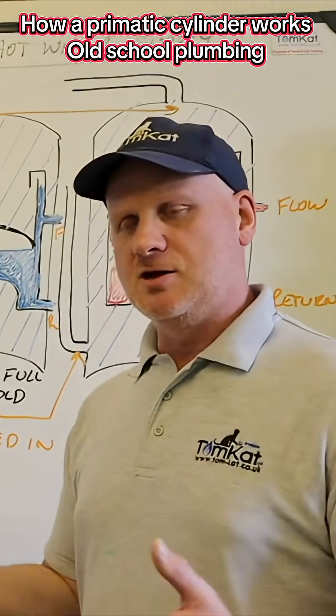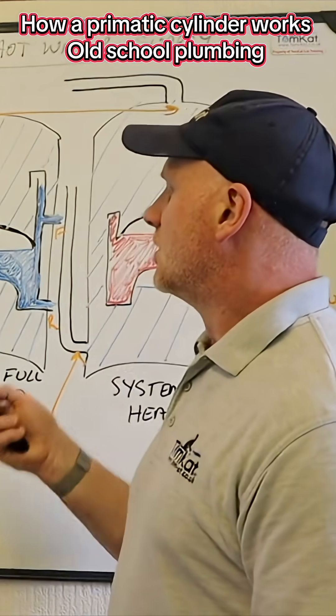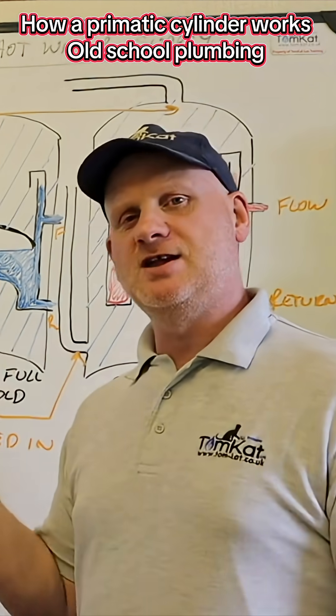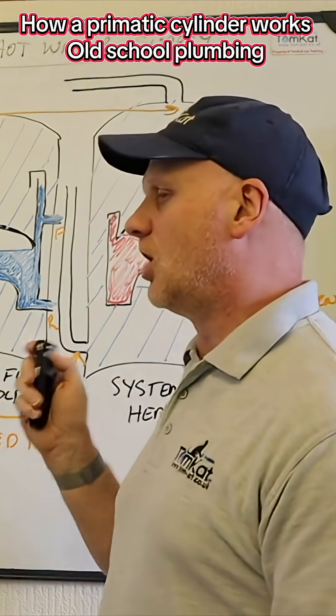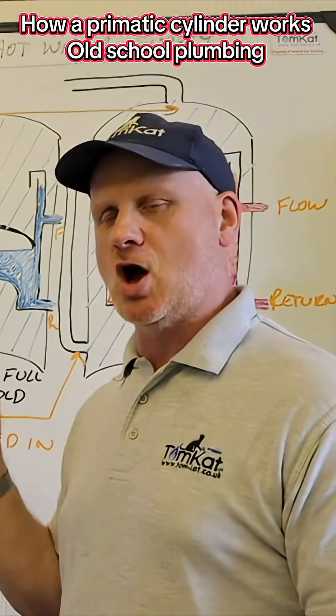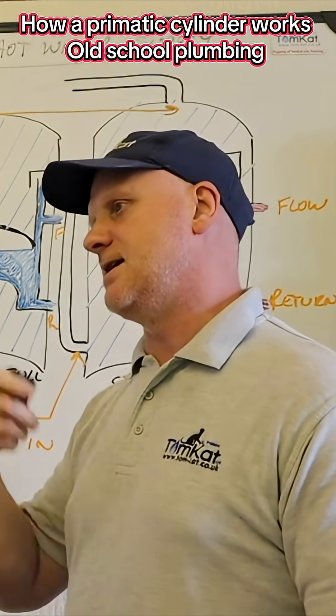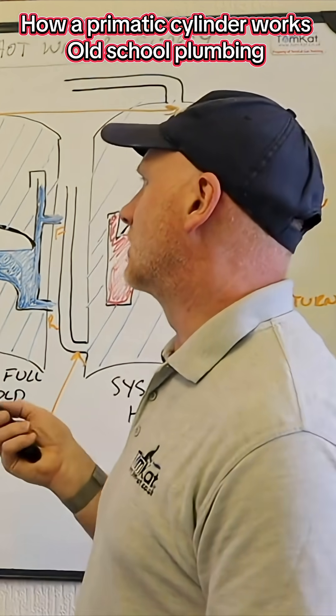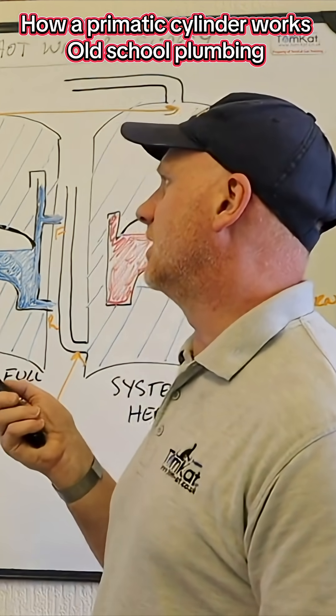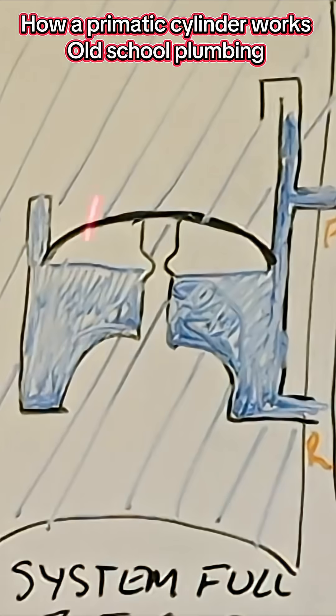So when you're initially filling and draining these cylinders, you should always have the hot tap open because the furthest away hot tap downstairs will get rid of all the air through the top here. Now then we're fully filling the system up now in the next one so you can see the actual primatic and the air bubble is in the top.